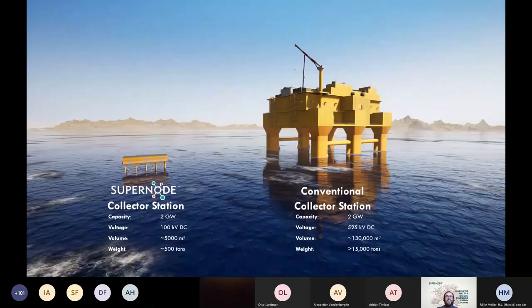I'd like to highlight the scale difference between a conventional converter station, based on the DolWin3, and the SuperNode converter or collector station—the size difference is vast. In the offshore environment, platform size really dictates huge cost, all driven by the voltage levels chosen for these schemes. As we move from existing 320 kV systems to 525 kV systems, platforms increase drastically in size, and the cost of these platforms and electrical equipment rises drastically.